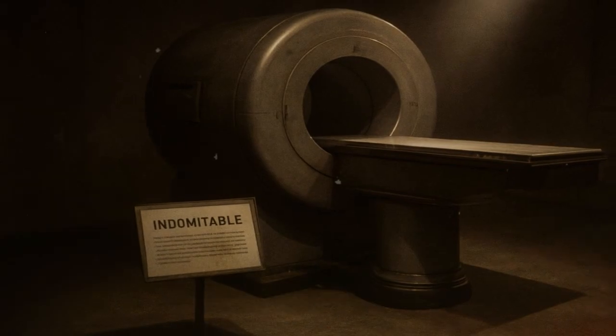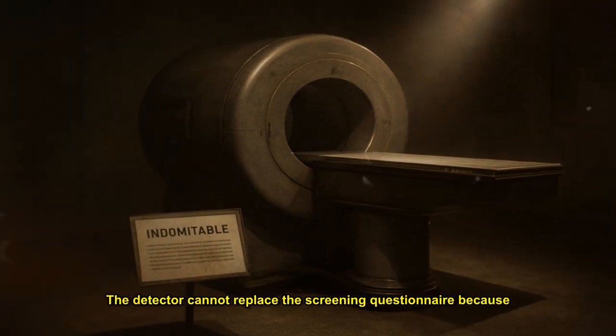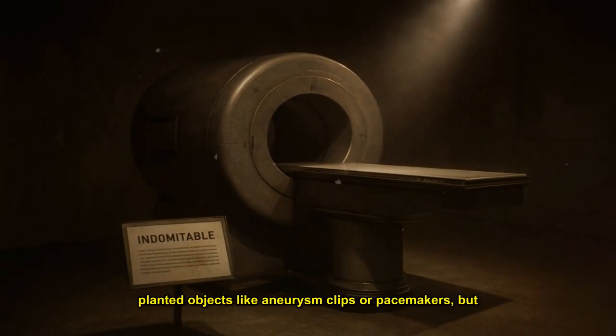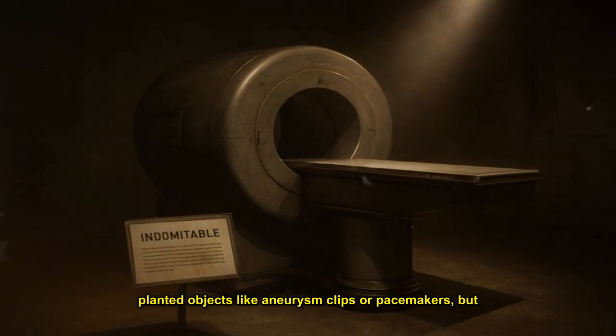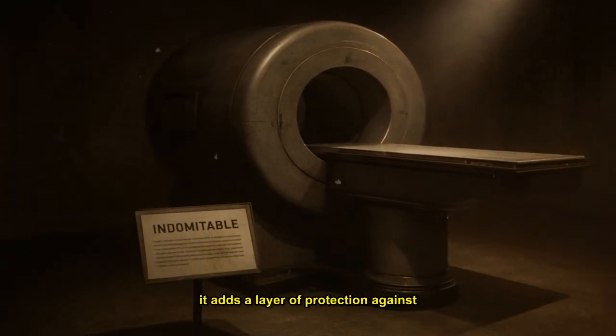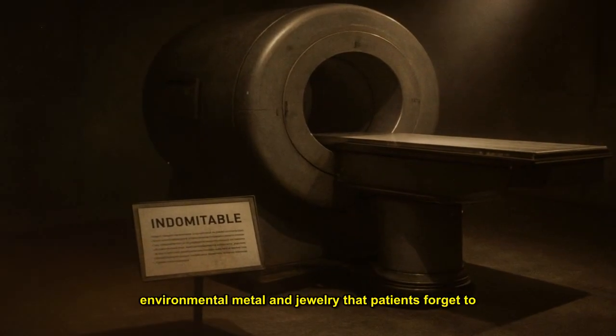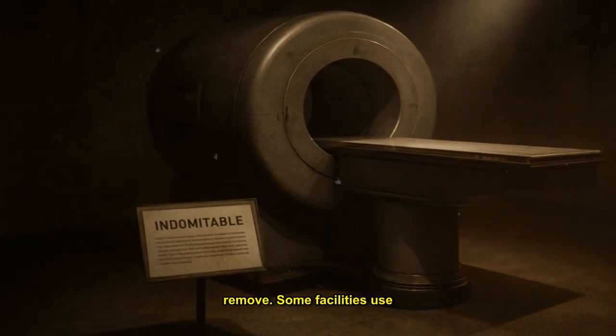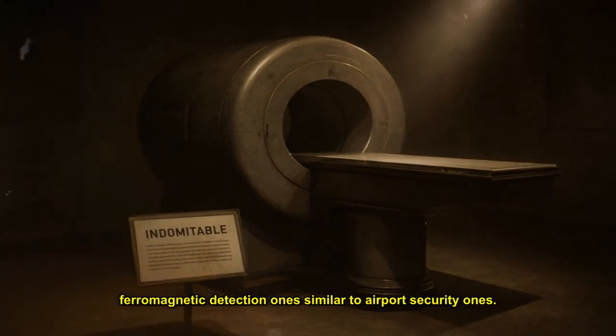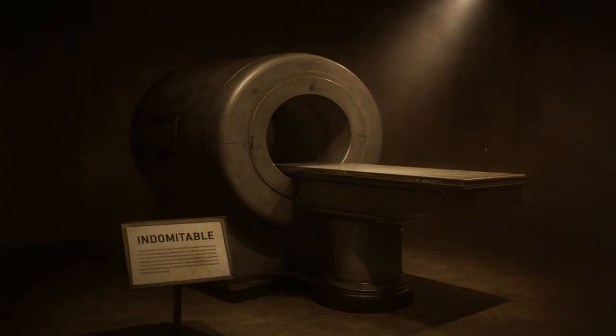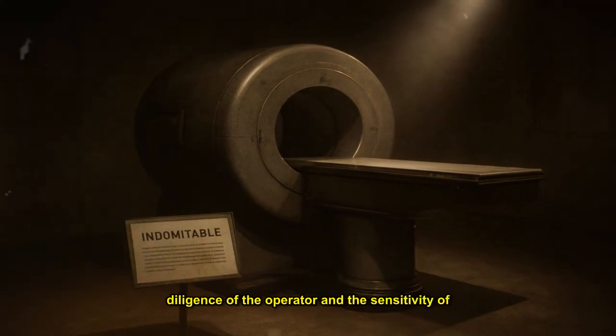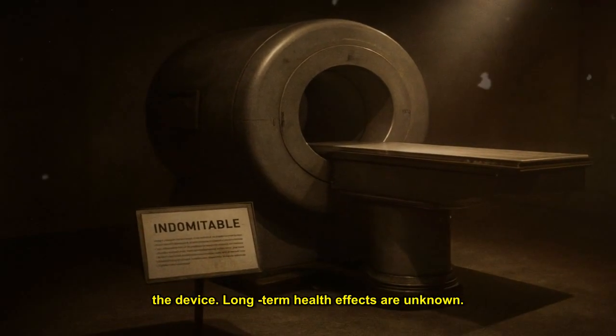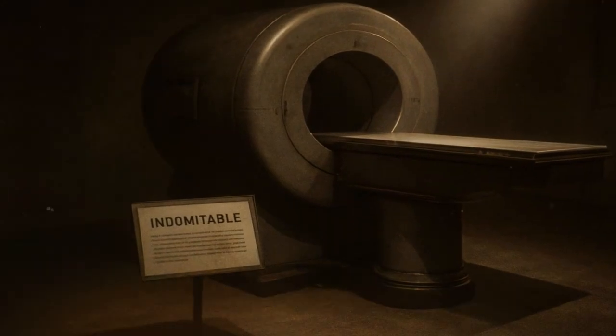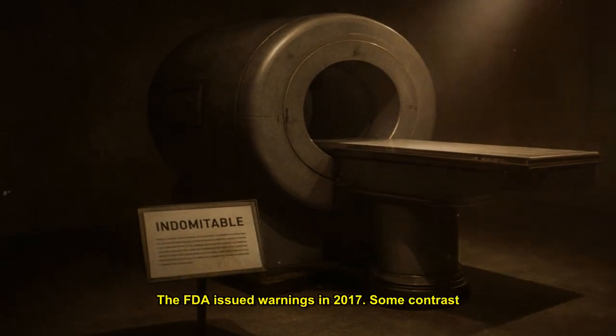Installation is straightforward. The detector cannot replace the screening questionnaire because it may not detect small implanted objects like aneurysm clips or pacemakers, but it adds a layer of protection against environmental metal and jewelry that patients forget to remove. Some facilities use ferromagnetic detection wands similar to airport security wands. Effectiveness depends on the diligence of the operator and the sensitivity of the device. The long-term health effects are unknown. The FDA issued warnings in 2017.